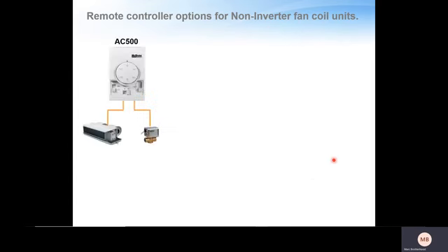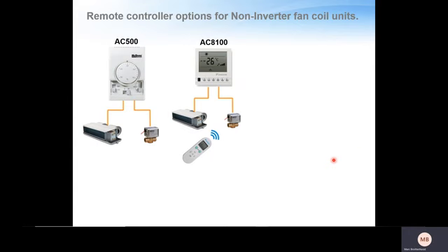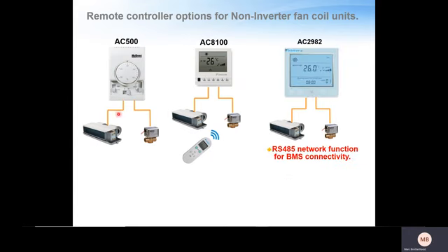So if we look at remote control options on larger systems for the non-inverter fan coil units, these are typically, you can have valve driving on all three remotes, as well as fan speed control. And this is, as mentioned, this RS485 network for BMS connectivity comes on the AC 2982 remote controller.